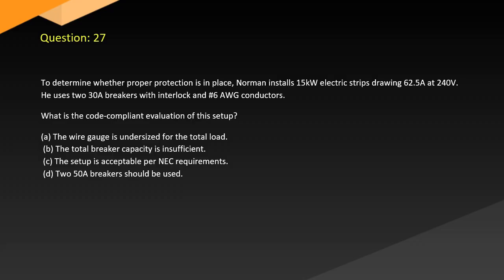Question 27. To determine whether proper protection is in place, Norman installs 15 kW electric strips drawing 62.5 amps at 240 volts. He uses 30 amp breakers with interlock and number 6 conductors. What is the code-compliant evaluation of this setup? A. The wire gauge is undersized for the total load. B. The total breaker capacity is insufficient. C. The setup is acceptable per NEC requirements. D. Two 50A breakers should be used.